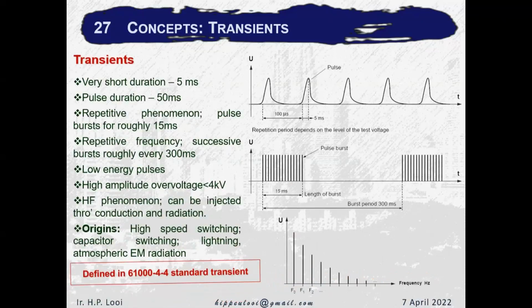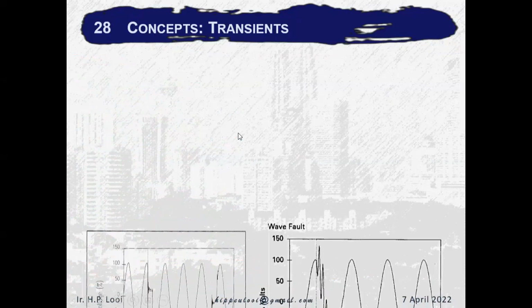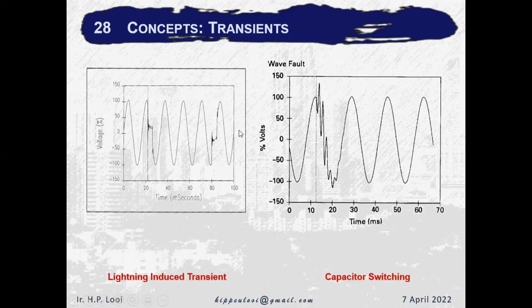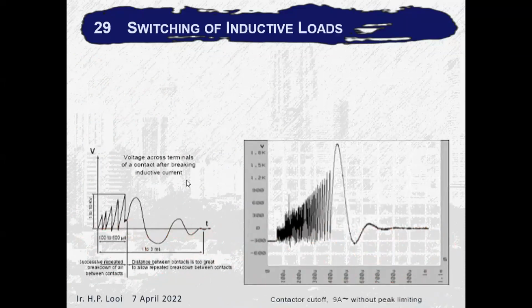Okay, transient is when you have a sudden surge which causes a spike in the voltage, a pulse in the voltage or current. Transient can be caused by switching, capacitive switching. Nowadays, as you know, all our lights are LED, and LED lights are capacitive in nature as compared to fluorescent, which is reactive in nature. So if you have a power failure and then suddenly you switch on a massive load of LED lights, you're going to get a spike in the voltage, which can cause a failure of insulation. Whereas this is how lightning-induced transient looks like. Switching of inductive loads, okay, I'm going to skip this.